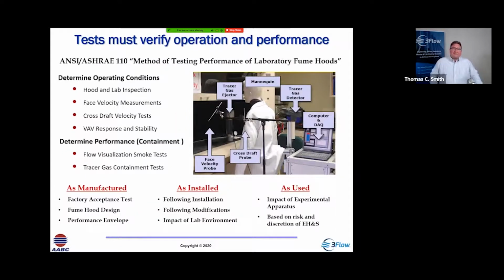So the ASHRAE 110 test was developed to evaluate hood performance, and it's divided into two basic sections. The first section is the definition of operational conditions. Under what conditions are the hoods operating? And under that set of operating conditions, how well does it maintain containment performance? And so when we look at factors such as face velocity and the air velocities in the room around the hood, or how the VAV system is responding and its stability of flow, those are evaluation of operational conditions. And under that set of conditions, we want to look: does it contain visually during a qualitative airflow visualization or a smoke test? Or can we quantitatively evaluate containment?